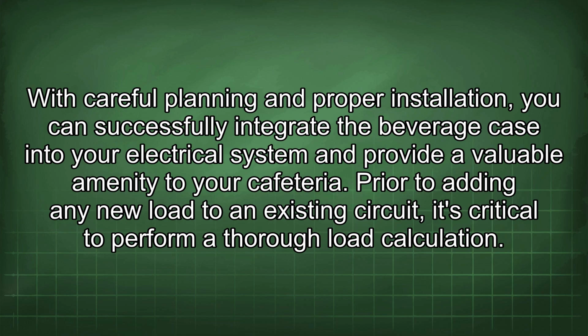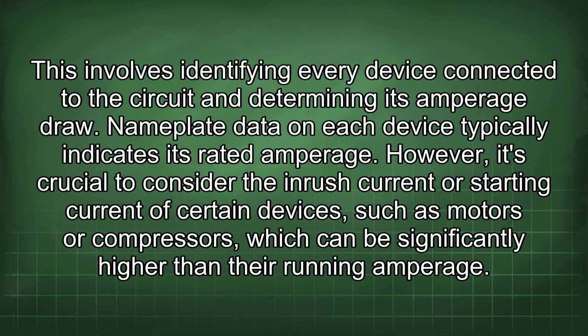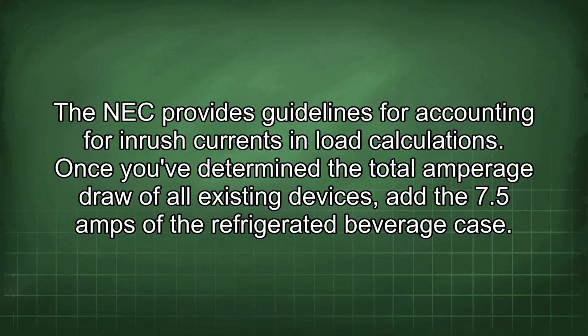Prior to adding any new load to an existing circuit, it's critical to perform a thorough load calculation. This involves identifying every device connected to the circuit and determining its amperage draw. Nameplate data on each device typically indicates its rated amperage. However, it's crucial to consider the inrush current or starting current of certain devices, such as motors or compressors, which can be significantly higher than their running amperage. The NEC provides guidelines for accounting for inrush currents in load calculations.